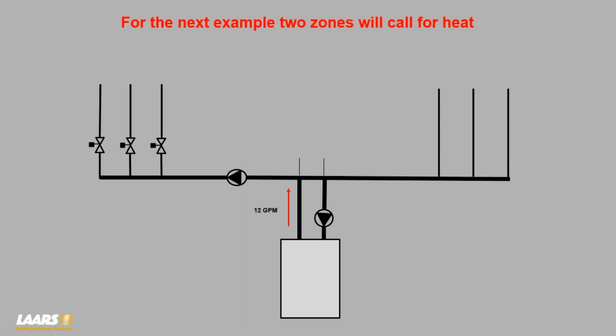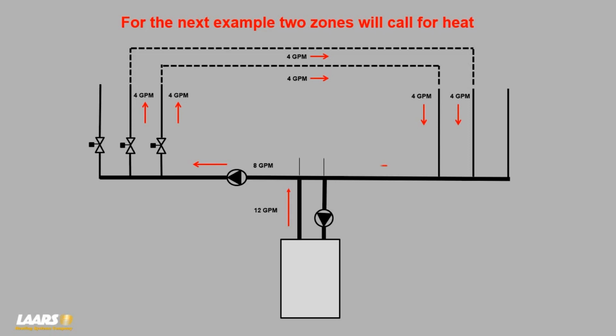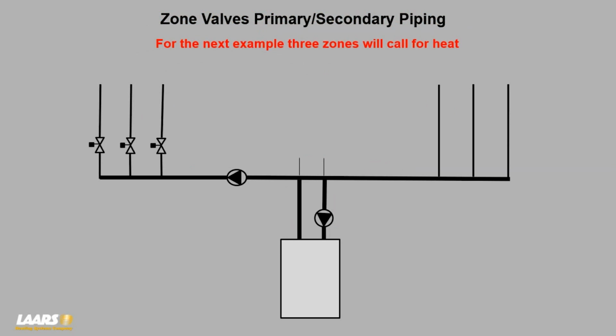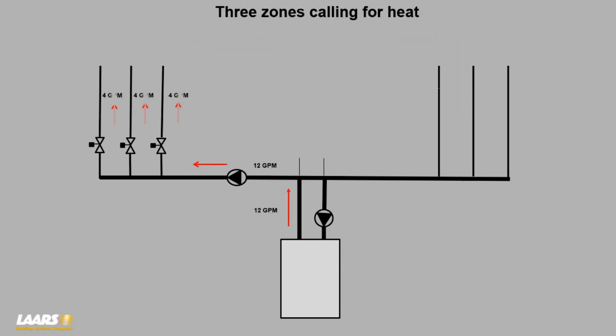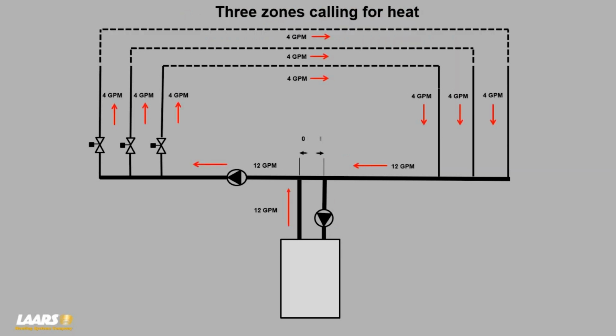With 2 zones calling, 8 GPM would travel down the manifold. Why? Because you get 4 for each zone. 8 returns, and in this example, 4 GPM will travel backwards, meeting up with the returning 8 GPM and guaranteeing the boiler its proper flow rate. If all 3 zones were calling, nothing travels through the 2 closely spaced T's.